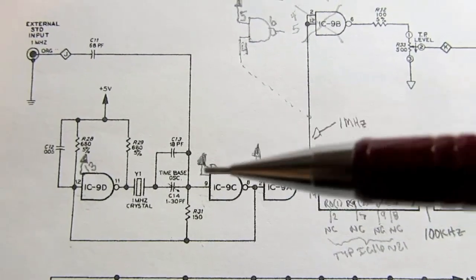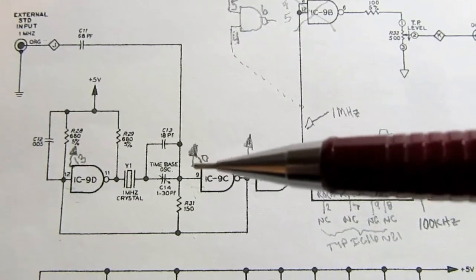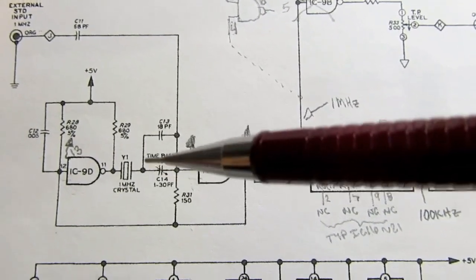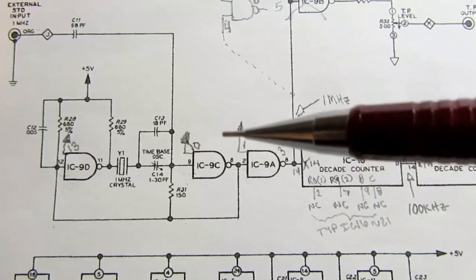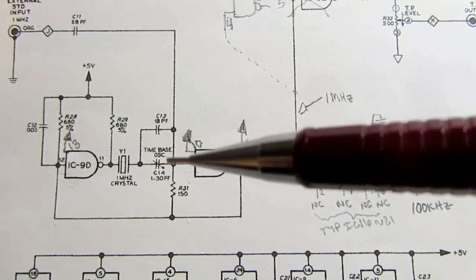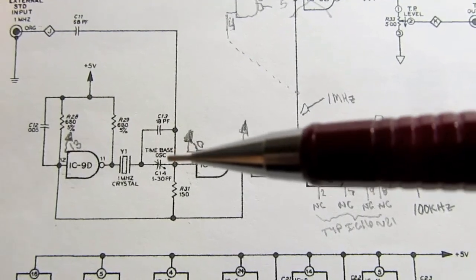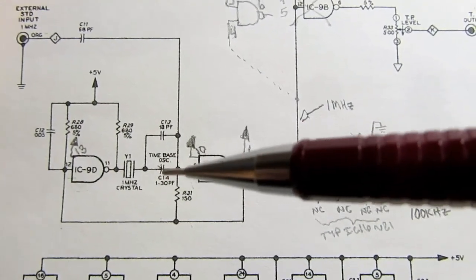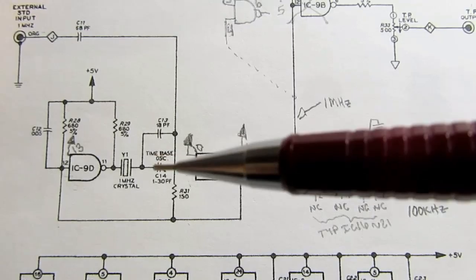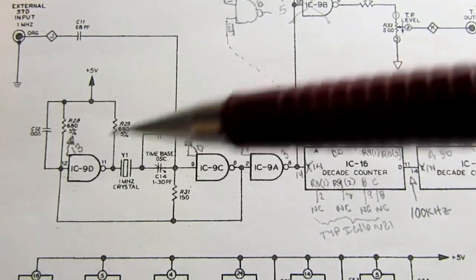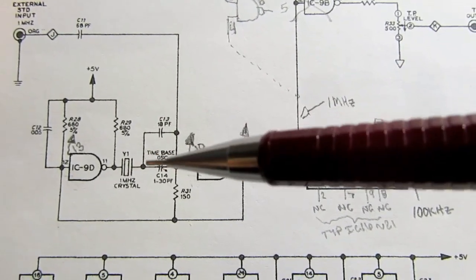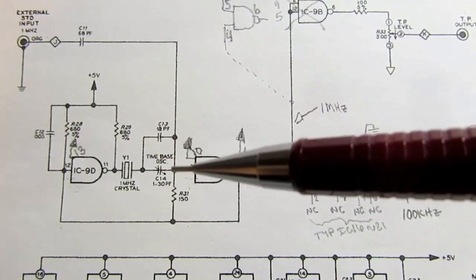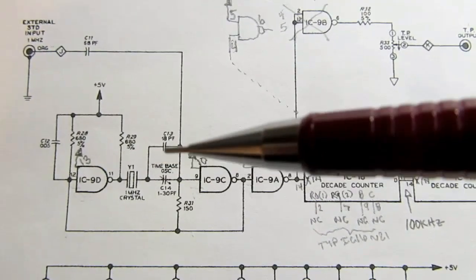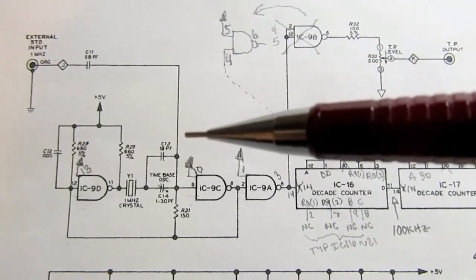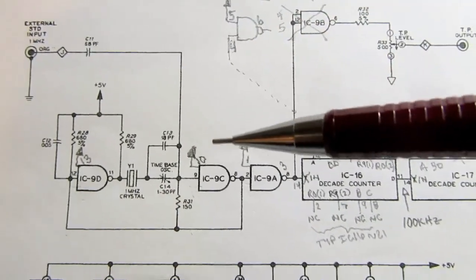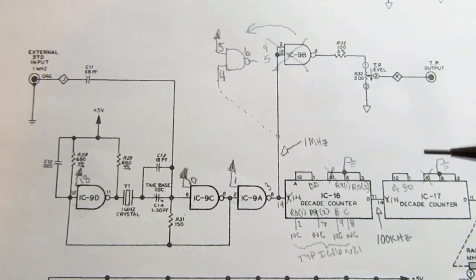And the more expensive professional frequency counters have oven-controlled crystals. So the crystal's held in a small chamber with a heater, and a circuit monitors the temperature and adjusts the heater to maintain an accurate temperature, and then you calibrate the oscillator for the desired frequency at that crystal temperature. And so this is not an oven-controlled oscillator here, and for that reason the rest of the circuit might be just perfectly fine. It is just digital after all.